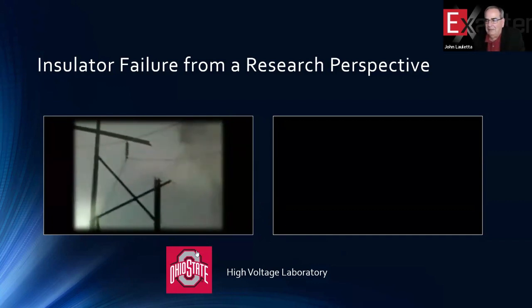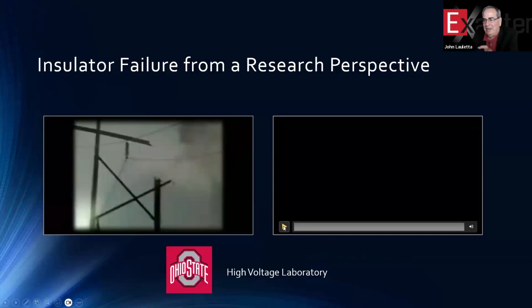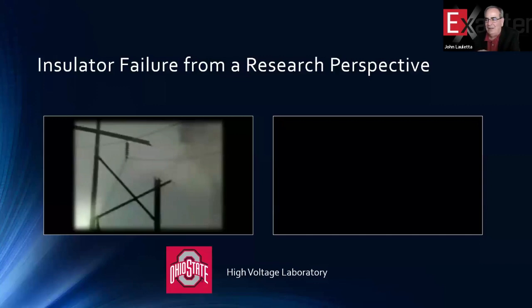So what we did in these studies, this is 2 parts of a 6-part series on our website that were laboratory investigations we did, and we put 2 insulators on 1 conductor on a cross arm, and we energized that to line voltage, and then we contaminated 1 insulator and left the other insulator clean. And we saw that the contaminated insulator in that video did have some arcing going on it. So let's look at it a little bit further down the test scenario, and you can watch this whole series of snippets of this laboratory study on our website at exacterinc.com.